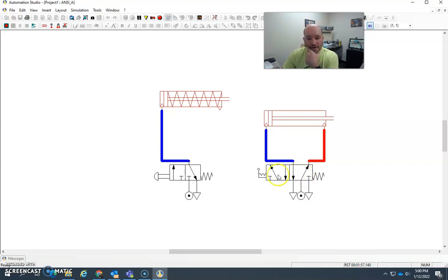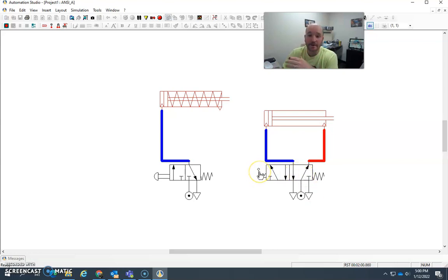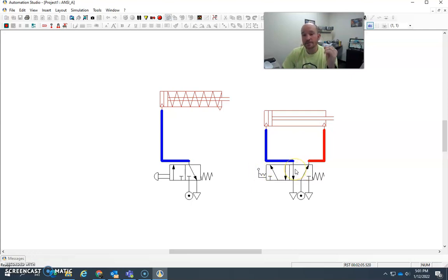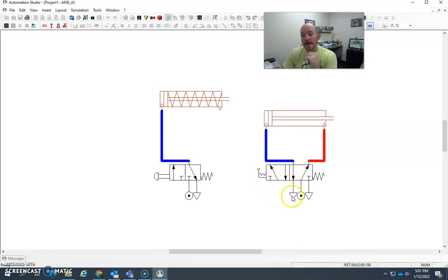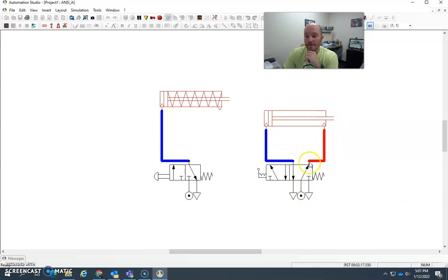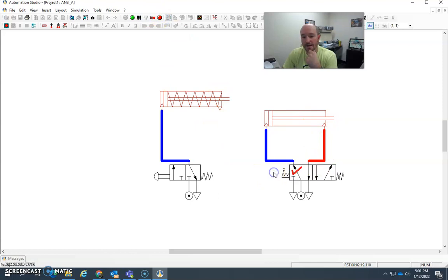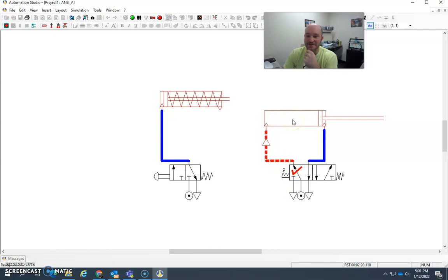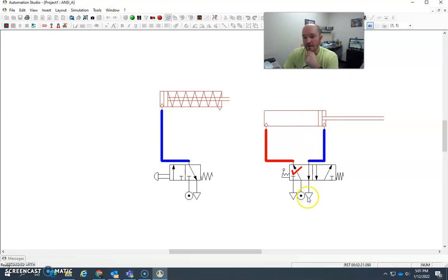But let's walk through how this works. So this, instead of a push-button here, what I have is a detent lever actuation. So when I activate this, the spool is going to shift and then lock into place, and air will then go from my pressure source here up to here and extend the cylinder. The air that is in here will be exhausted out. So let me go ahead and put this in slow motion, and we can watch it happen. So now air is flowing up through here. I guess that wasn't very slow. Air flew through to here, and the air on the other side of the cylinder flew back down to the exhaust.